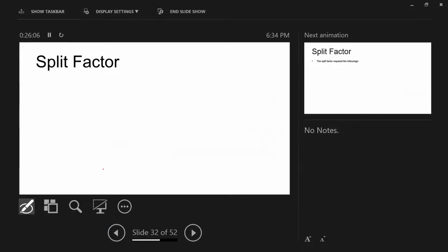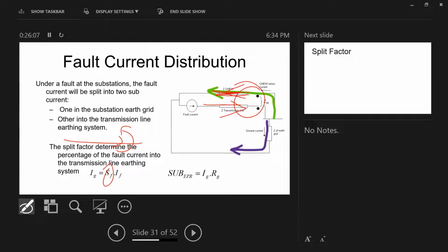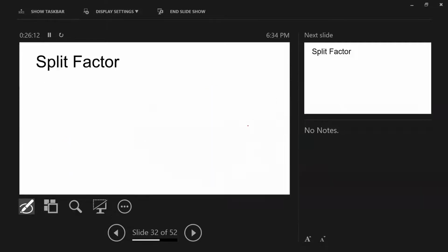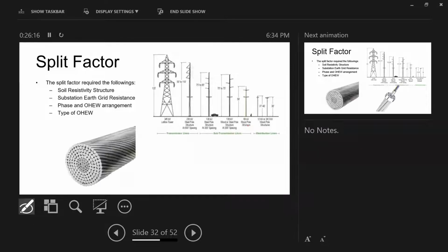No. And we all know that the substation depends on the current that goes into this amount. Now, for a split factor, all these are important. To determine the split factor, on top of the soil resistivity, what determines it is the layout and also the type of overhead earth wire. By the way, it's an optic ground wire.